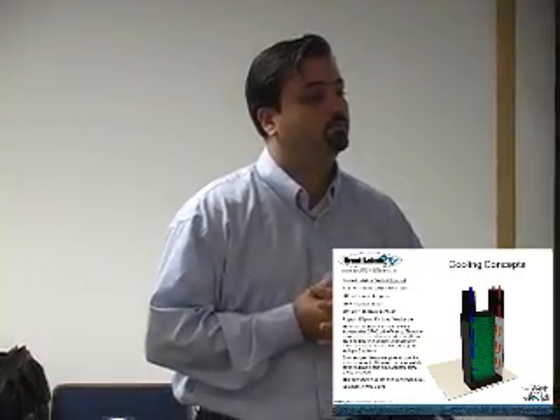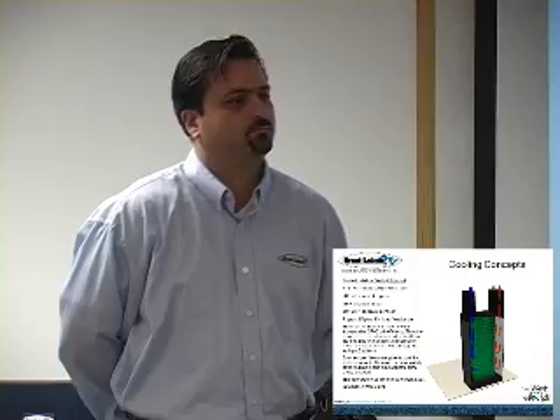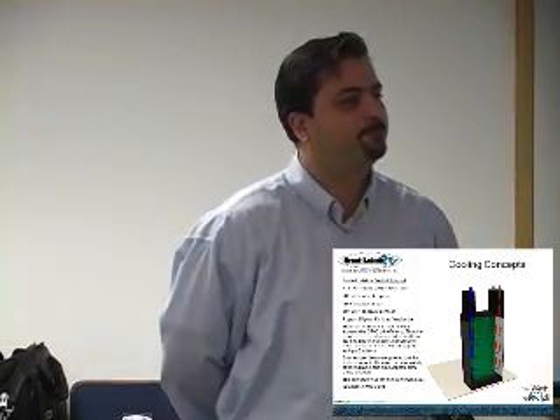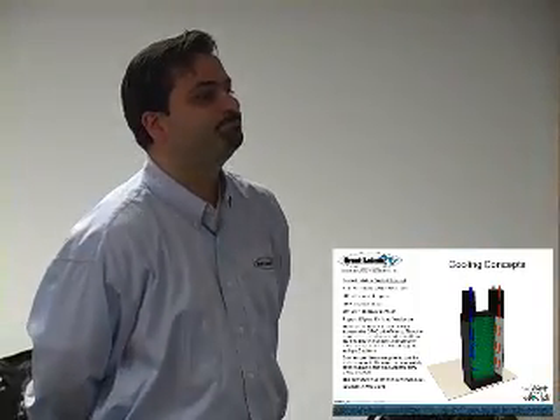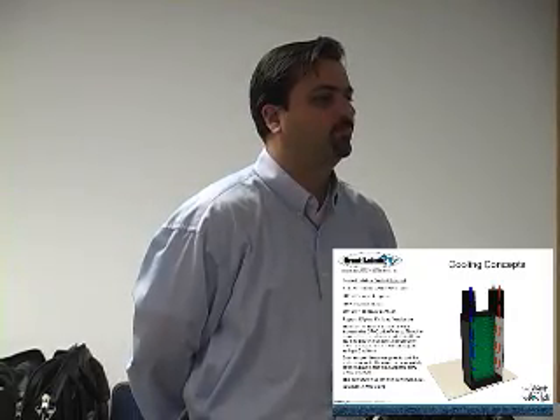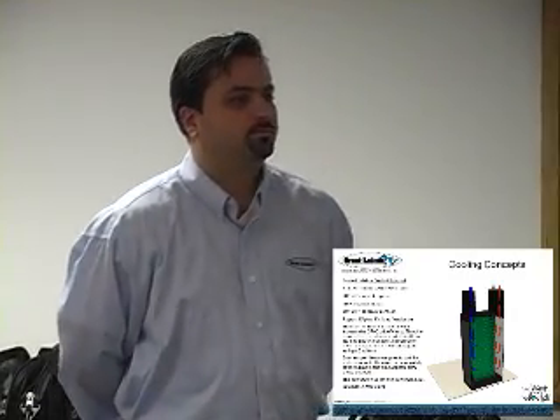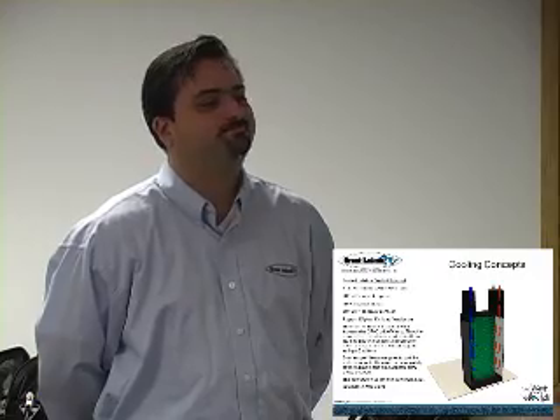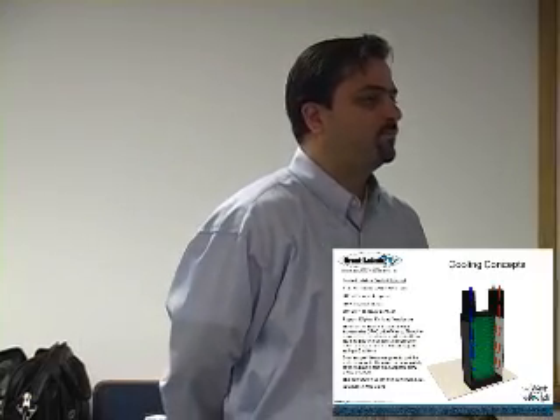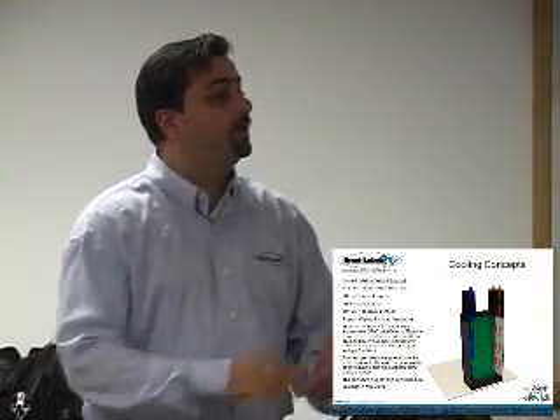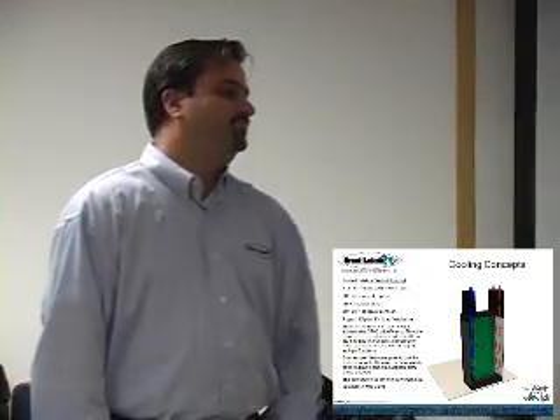For the cold aisle, I noticed that our cabinets are pretty set far apart from the rows. In the cold aisle, what do you recommend as far as spacing for the cold doors? We have slide-out servers, so how much space is good so they're not too far apart, so that we're not cooling the whole room, trying to get that air in front to get some through.